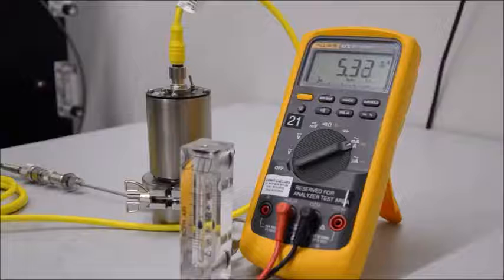You can see that the sensor is settled between 5.32 milliamps and 5.33 milliamps, which puts the reading around 82.5 ppm to 83 ppm, which is within our plus or minus 2% of 83 ppm. Once we have verified that the calibration is correct, we're going to switch back to our sample gas and we're ready to go.